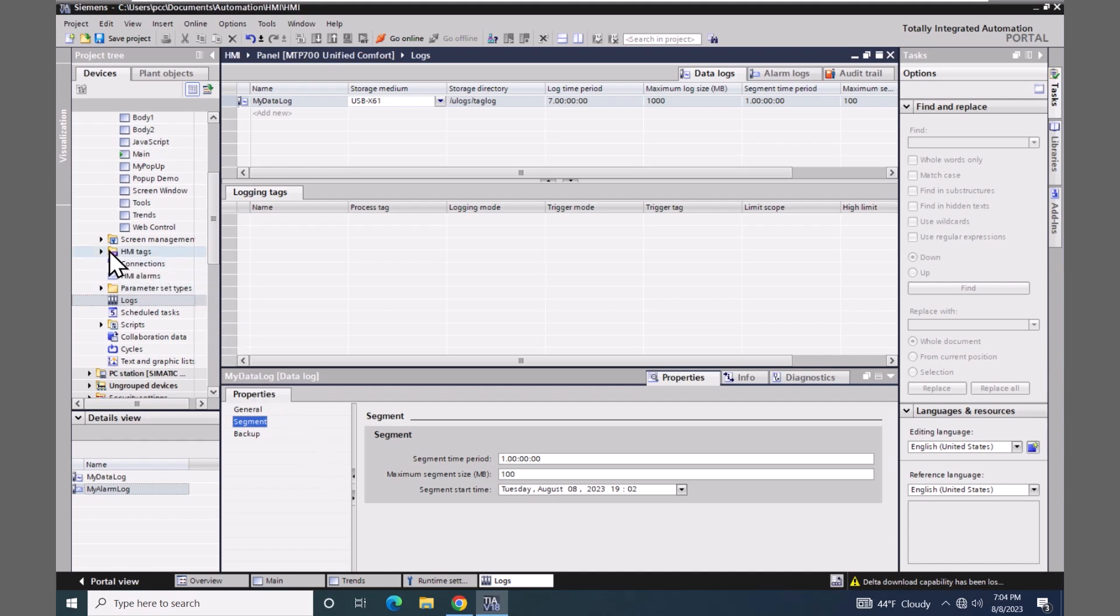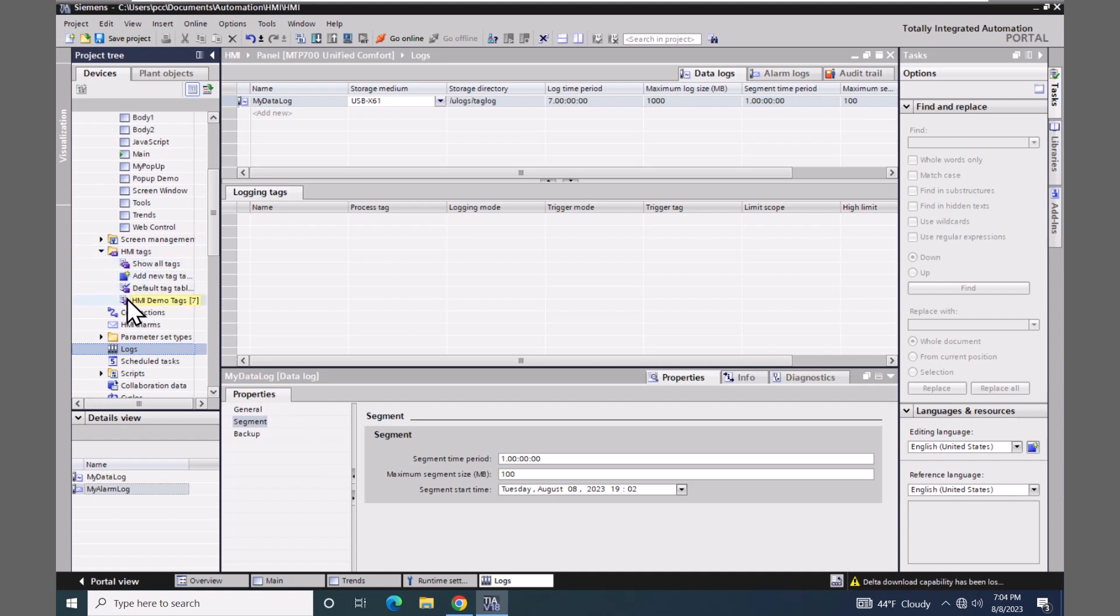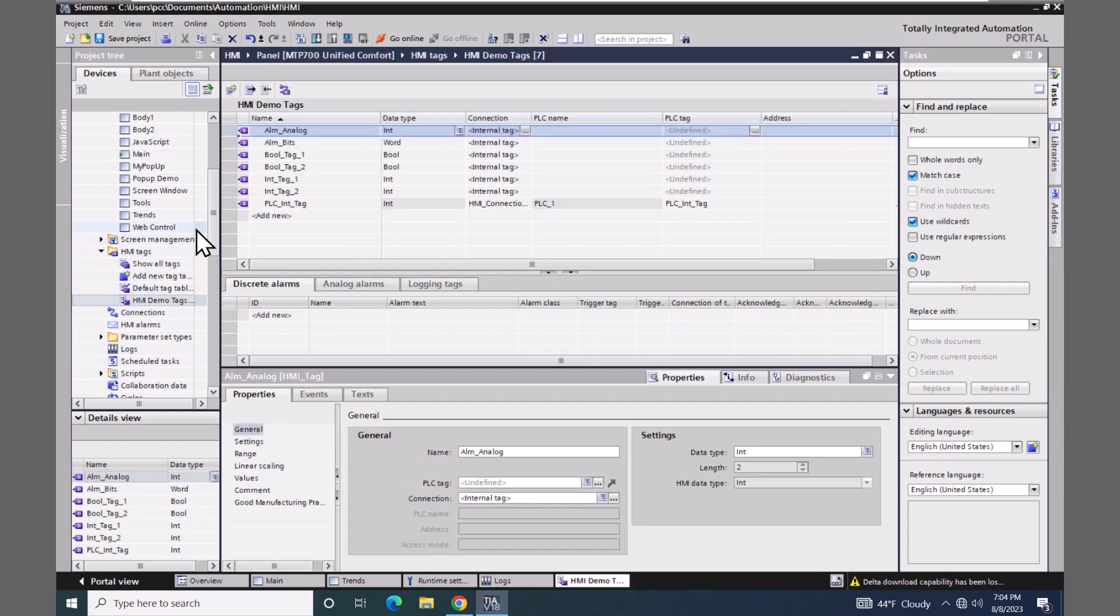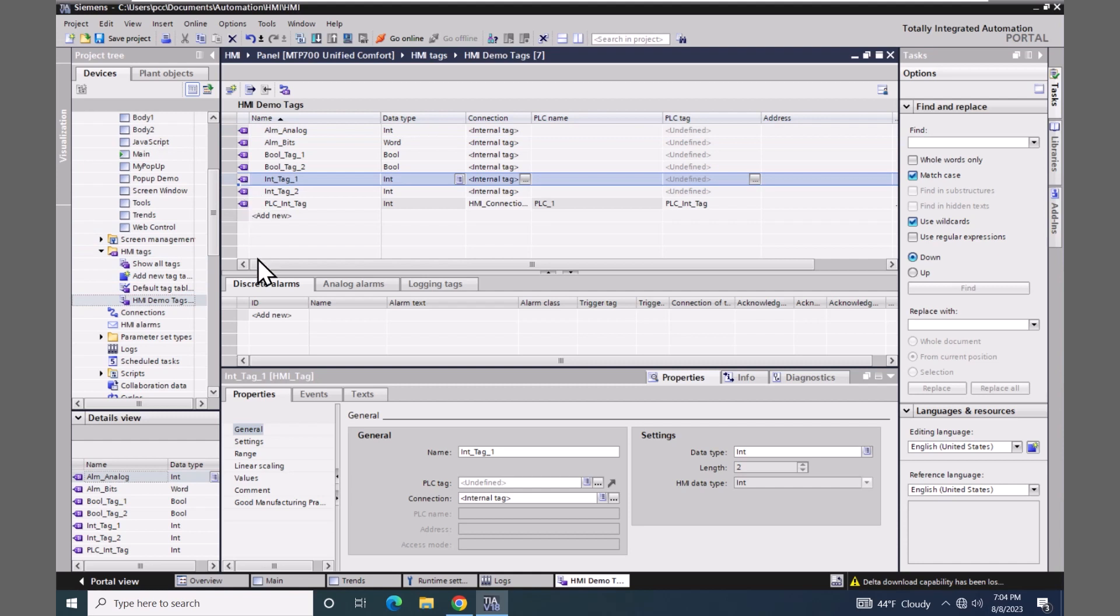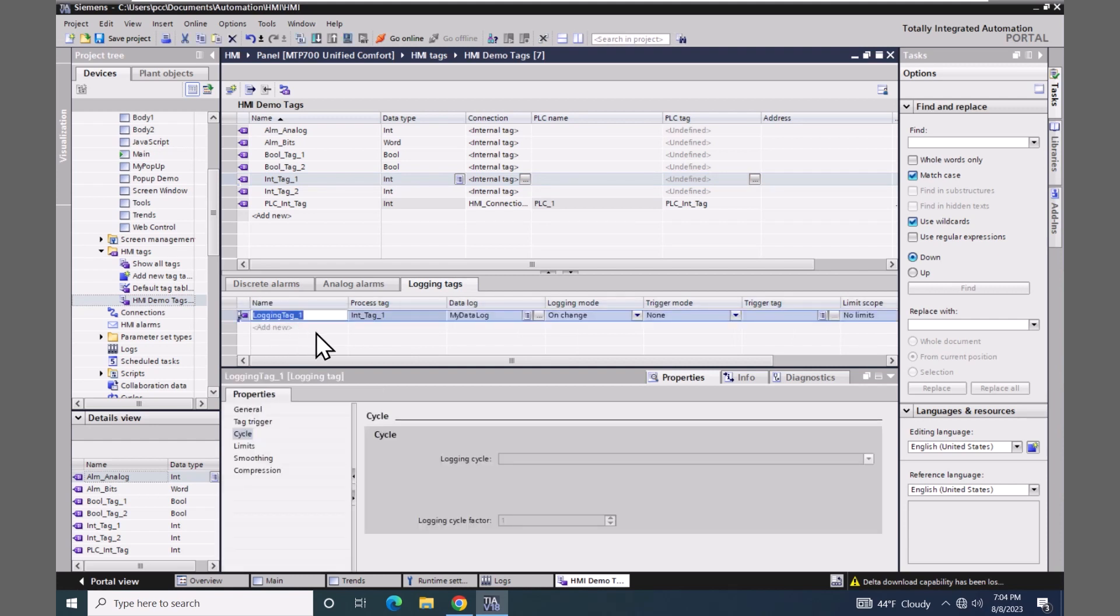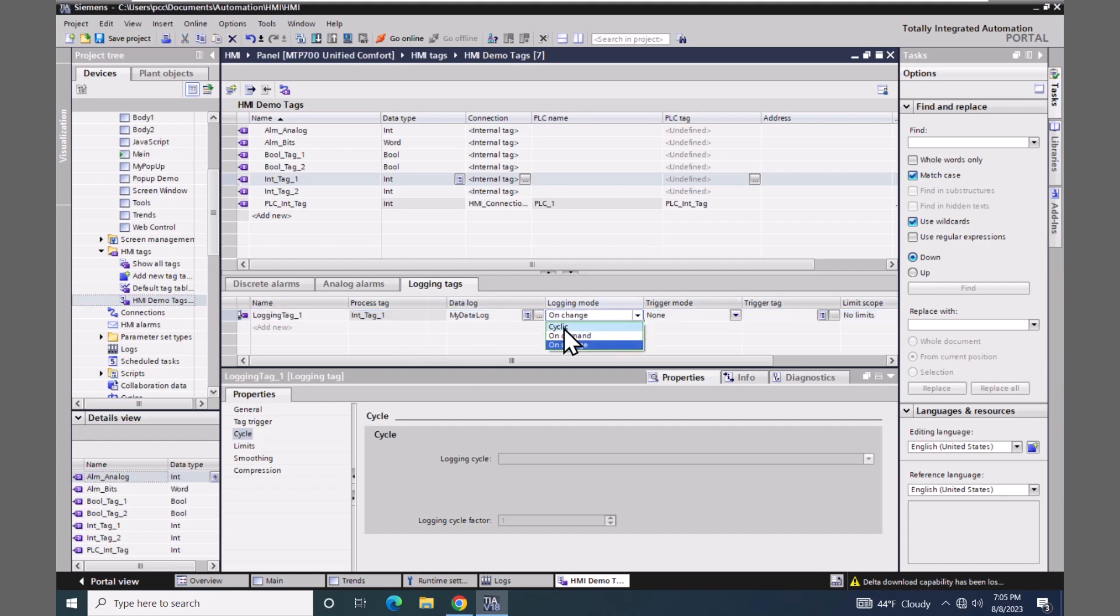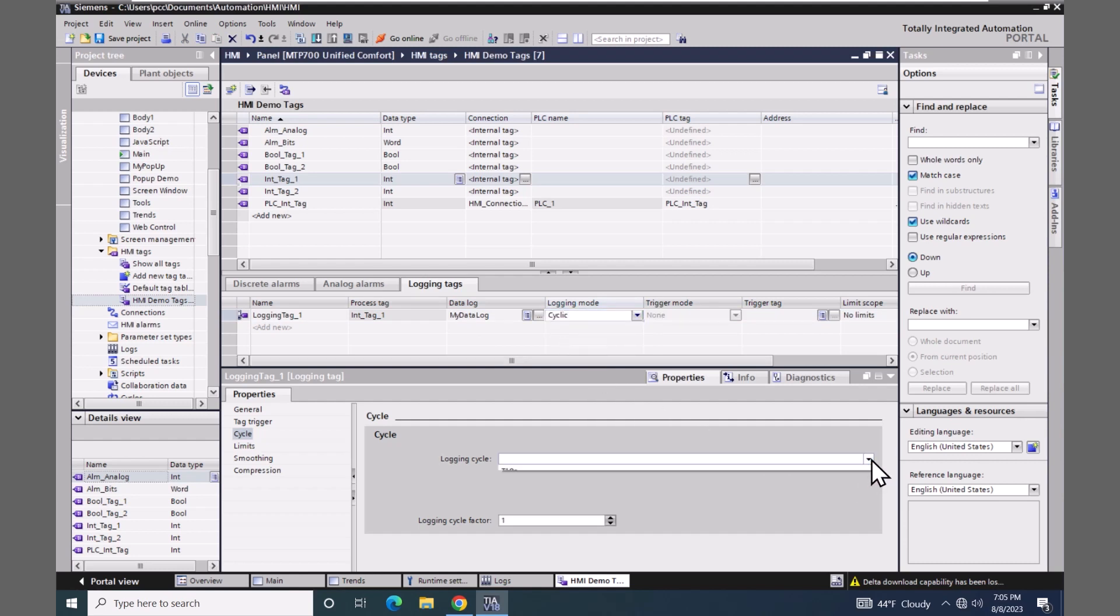Now I will go up to the HMI tags area, open up my HMI demo tags tag table, and select my integer tag one. And then in the middle window here, there is a tab for logging tags. So I will select add new. I'll just use the default name of logging tag one. Because of the integer tags that I picked up above, it already assigned the process tag value. So I can configure in this table editor. The logging mode is set to on change. I'm going to change that to be cyclic and then set the time interval of two seconds.